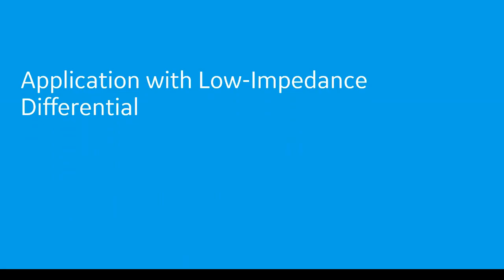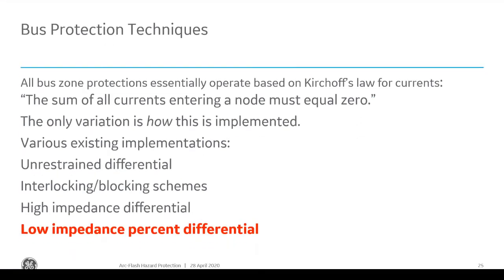Low impedance bus differential. We'll talk a bit about low impedance bus differential, but before we do, I just want to mention some of the other bus techniques out there. I mentioned the unrestrained differential, which is basically the overcurrent one on the pole. I mentioned the zone interlocking or blocking scheme. There is also high impedance bus differential. We just don't have enough time to talk about all of them today.